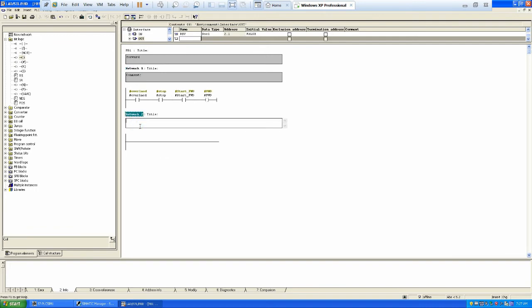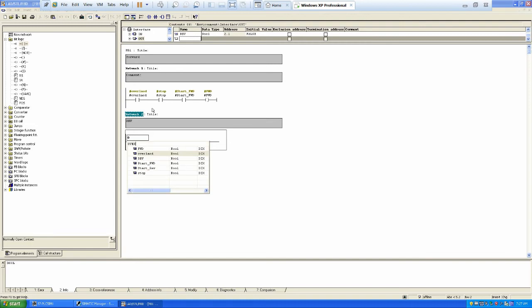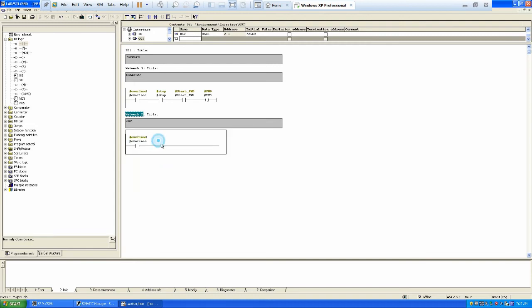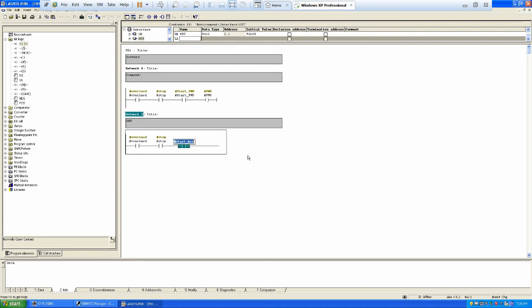Now it's time to define the network for reverse. For reverse, we will do the same thing — we will check the overload, just to check the interlock, and we can see the stop as well. Then we can see the start command — the start button is in normally open condition in the field. So start reverse, and then we have the output Q0.1 for reverse.